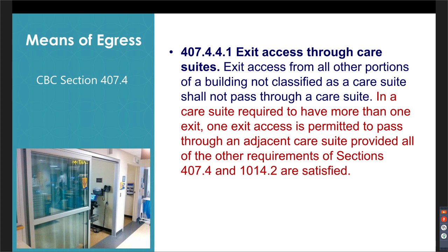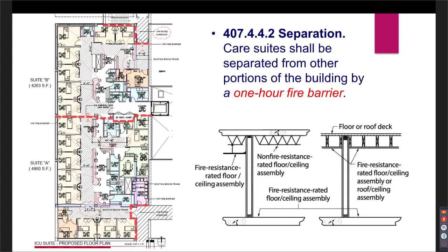You have this care suite, and they're required to have two exit accesses. One of them can go through another suite. The other has to go right to a corridor or an exit. And clear separation requirements for care suites: it's required to have a 1-hour fire barrier.